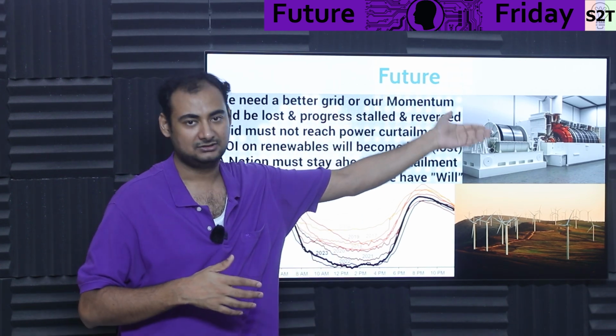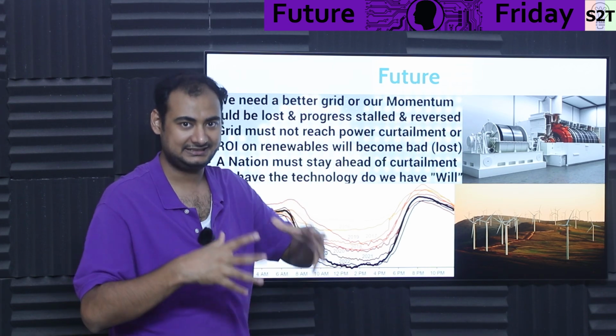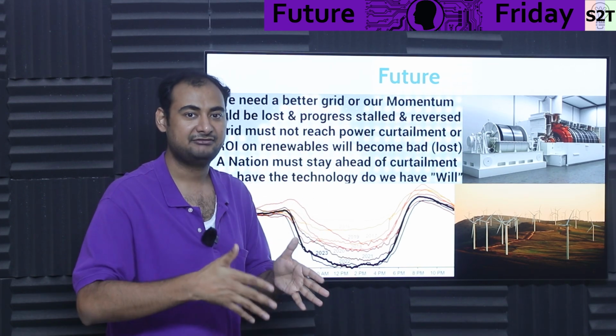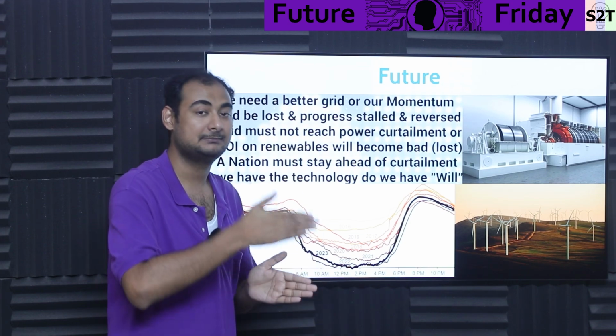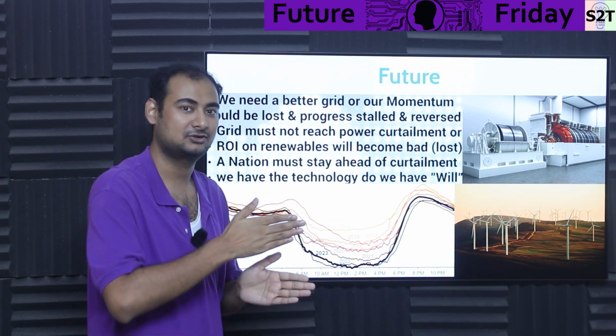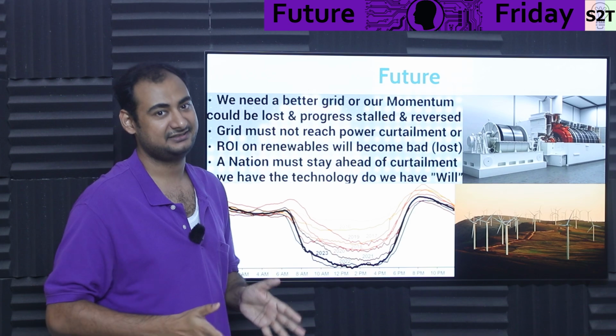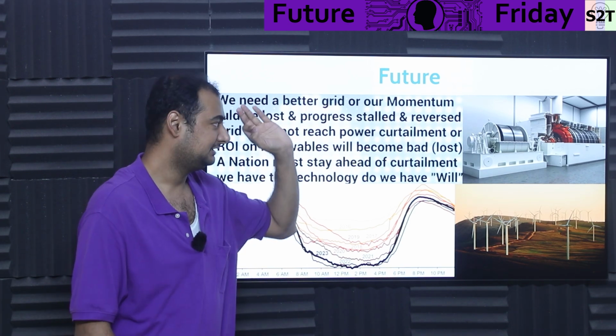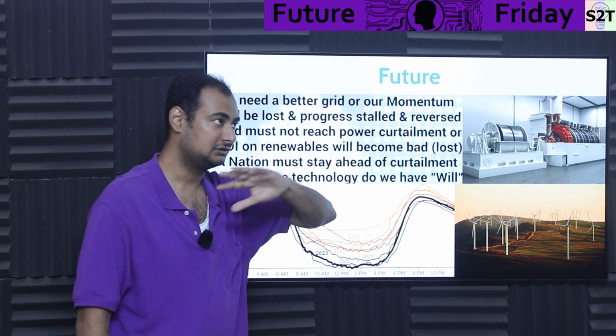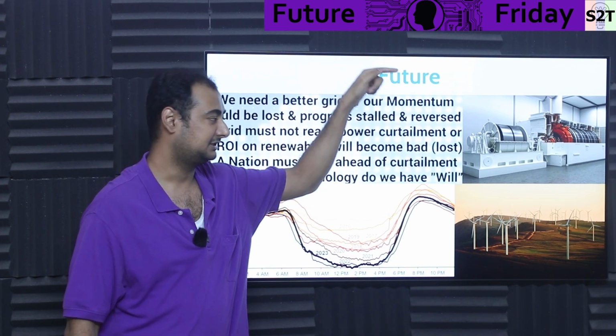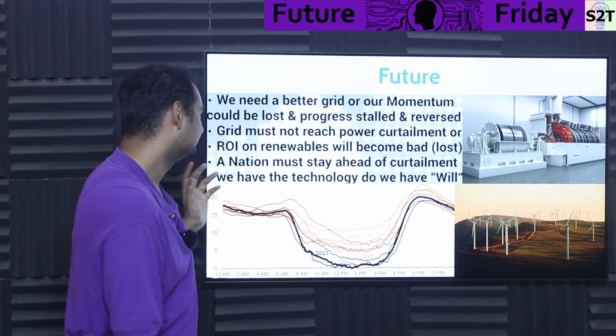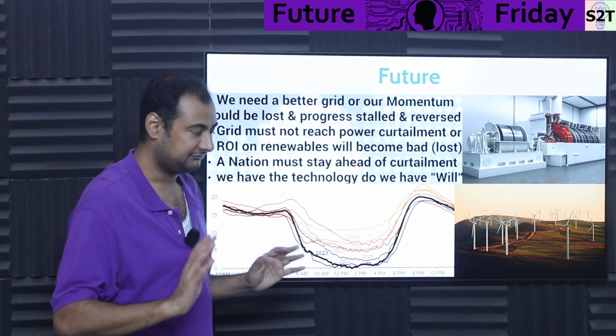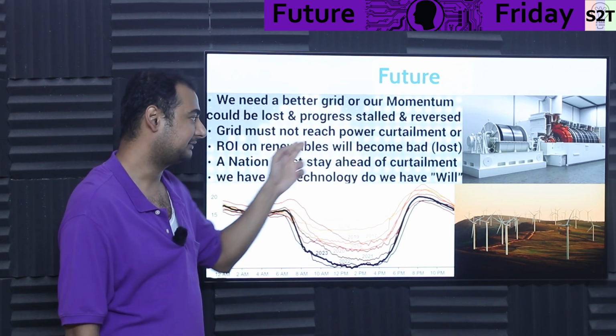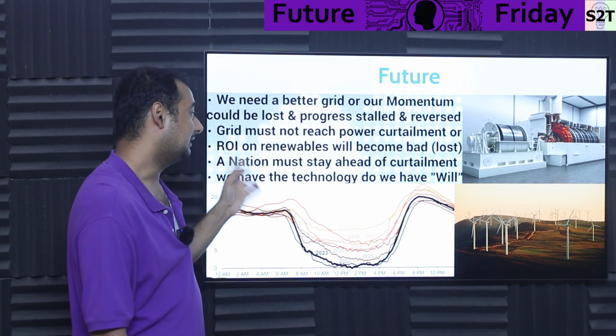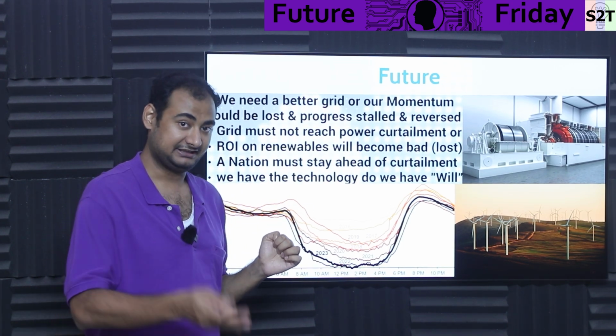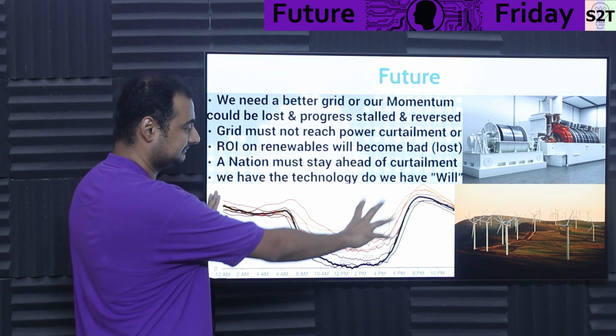Basically, the stator is creating the waveform, and that waveform is the master waveform. And because it's magnetically coupled to a mechanical rotating mass, it has inertia, absolute inertia. Now every inverter in the system, all the wind turbine inverters, is like, this is the master, follow this. So we solved that problem. Every problem can be solved. And we cannot allow power curtailment to happen, so ROI on renewables would become bad if that happens. And this is a problem.